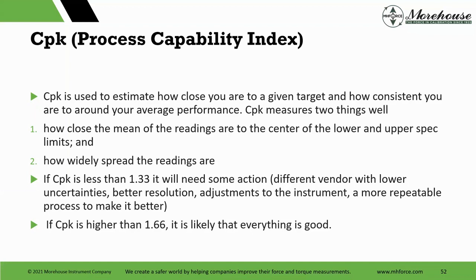But for our purposes, if we use it, it's how close you are to a given target and how consistent you are around your average performance. And it measures two things very well: how close the mean of the readings is to the center of the lower and upper spec limits, and how widely spread the readings are. So if we look at this, just simple numbers, if the CPK is less than 1.33, it might need some action. You know, a different vendor with lower uncertainties, better resolution, adjustment to the instrument, a more repeatable process.